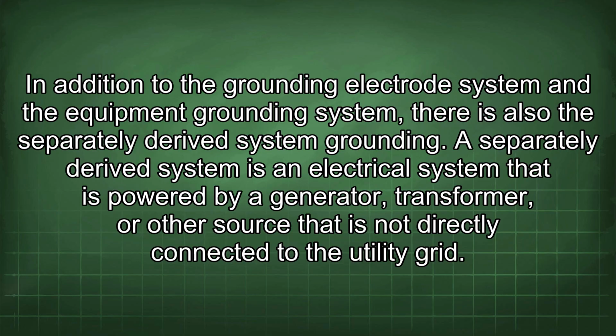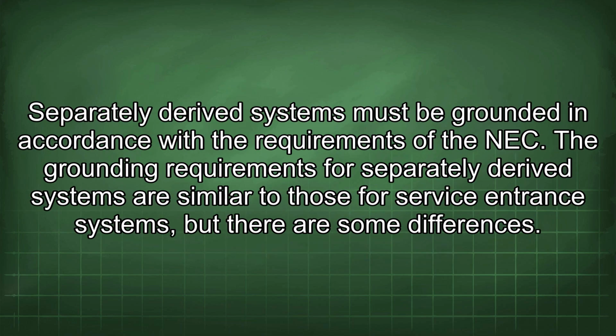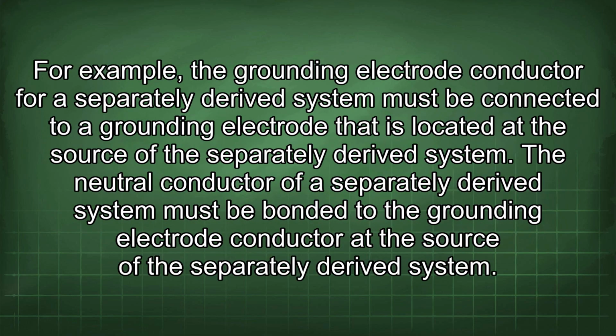In addition to the grounding electrode system and the equipment grounding system, there is also the separately derived system grounding. A separately derived system is an electrical system that is powered by a generator, transformer, or other source that is not directly connected to the utility grid. Separately derived systems must be grounded in accordance with the requirements of the NEC. The grounding requirements for separately derived systems are similar to those for service entrance systems, but there are some differences. For example, the grounding electrode conductor for a separately derived system must be connected to a grounding electrode that is located at the source of the separately derived system.